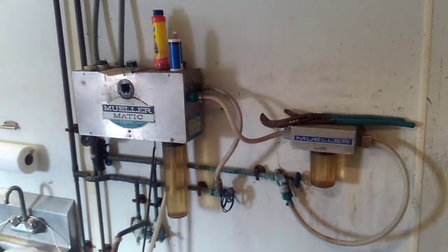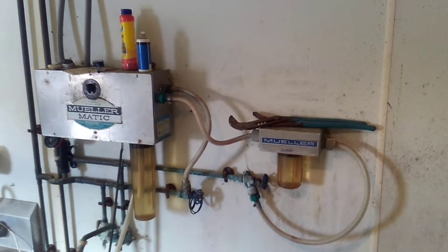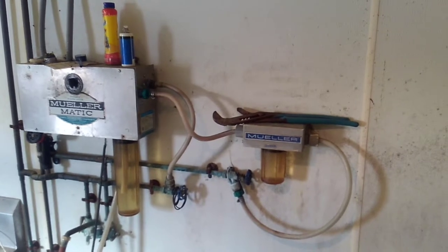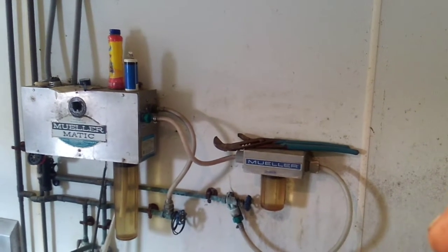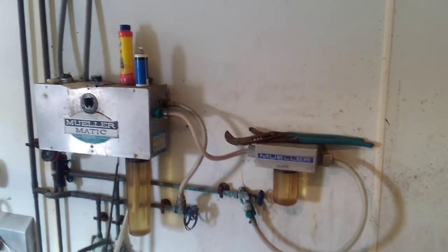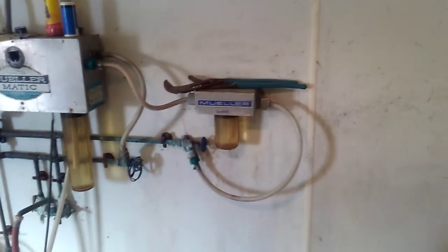And there's a timer on that. About every hour, when it's turned on and there's milk in here, the agitator will run for about 4 or 5 minutes, and they say it keeps everything stirred up. This is all on automatic. You've got a thermostat and an automatic refrigeration unit. If the temperature creeps up a little bit, it kicks on, cools it down, and keeps the milk under 38 degrees. You set the tanks as cold as you can get them without building ice up in the tank, because when you build ice up, that affects the butterfat tests.